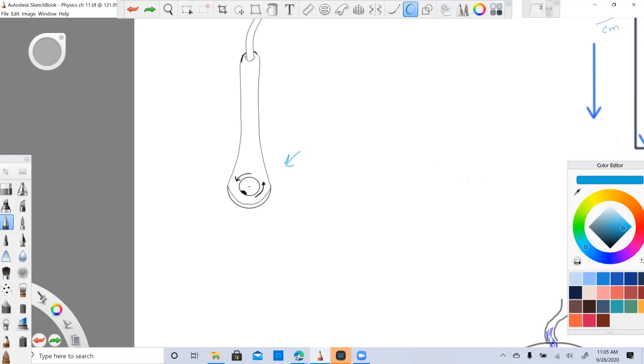Mechanical transducer, first one. Mechanical transducer contains a single circular disc-shaped active element that is physically moved. This movement creates a scan plane. So we already spoke a little bit about a circular element, kind of like shaped like a coin. And, anyway, a single element and how a single element will actually produce a natural focus and all that.